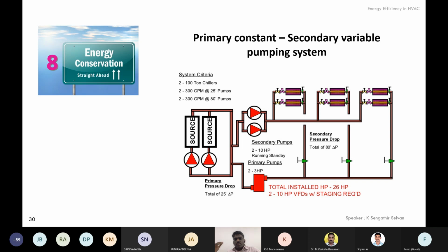So when the load is hugely pulsating at the AHU level, it is not necessary to always circulate the same amount of water. We can circulate only the required amount of water based on the load. That is why this concept came, the secondary variable pumping system. Now the right side secondary pumps will be fitted with VFD, and modulated to meet the load. But there is a small issue: the source, that is the chiller, needed, in olden days, a constant flow of chilled water inside the evaporator, only to maintain some velocity over the coils. That was in olden days. Nowadays there are chillers available which can take a minimum flow rate of 60%.